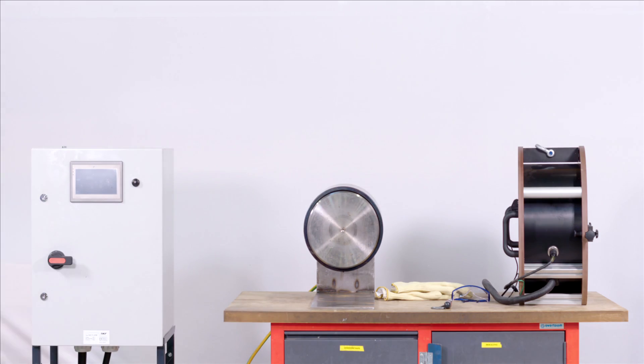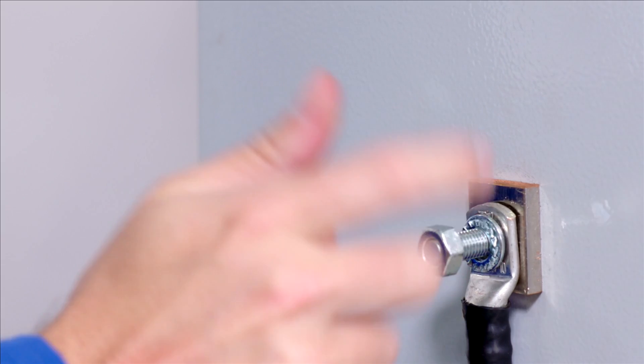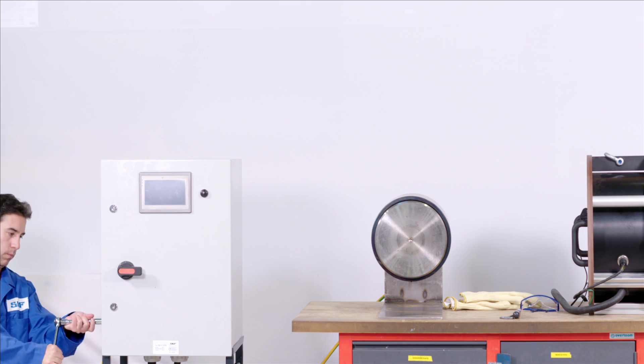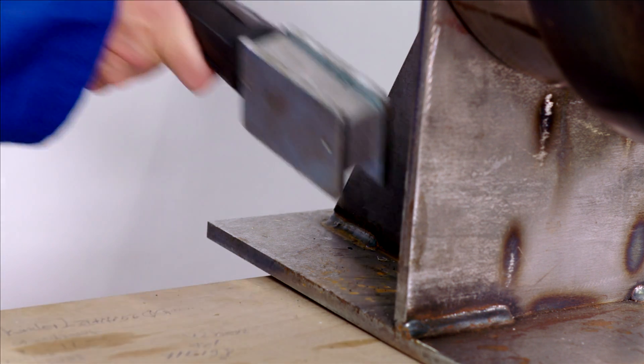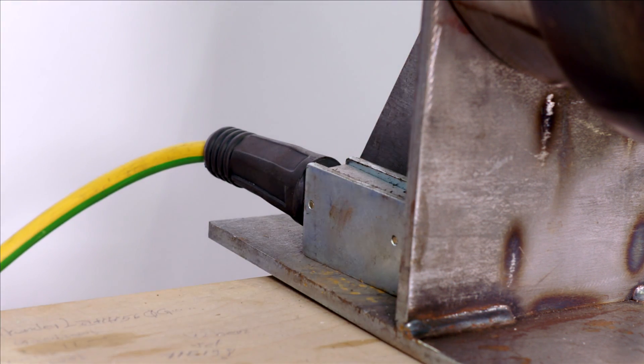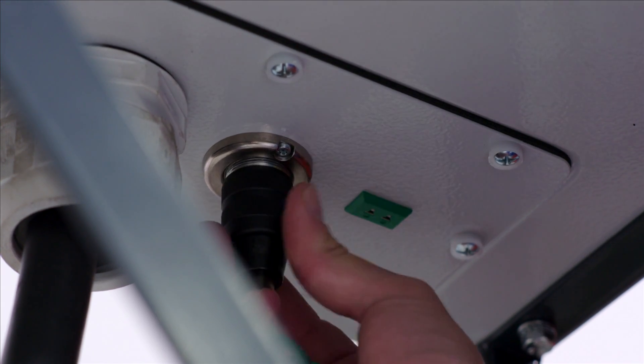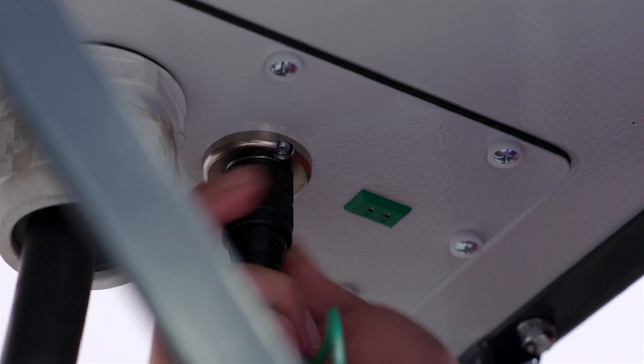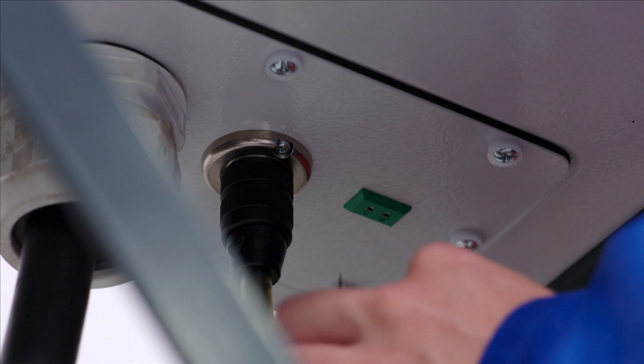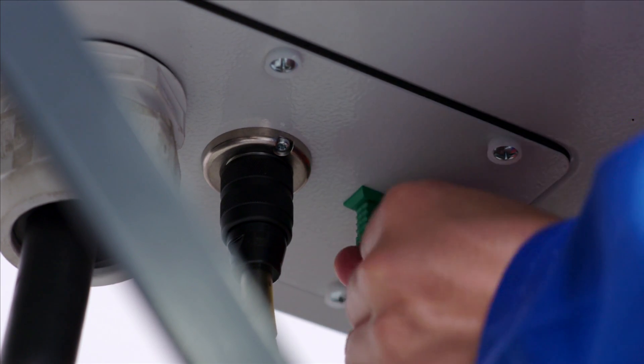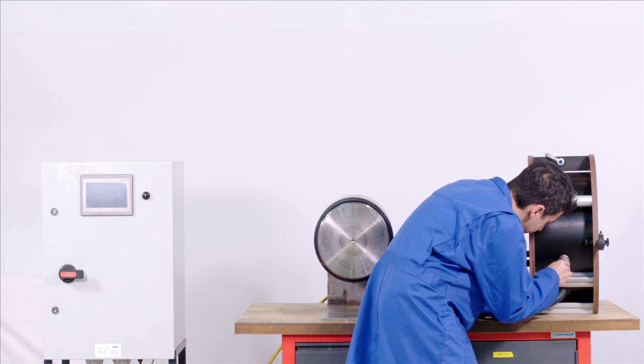Now earth the shaft by connecting the grounding cable to the control cabinet box. Then connect the magnetic clamp to the shaft. Connect the control cable to the box, and then the temperature probe extension cable to the cabinet. Now connect the control cable to the heater.